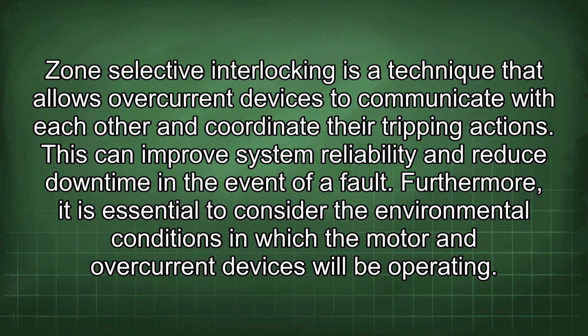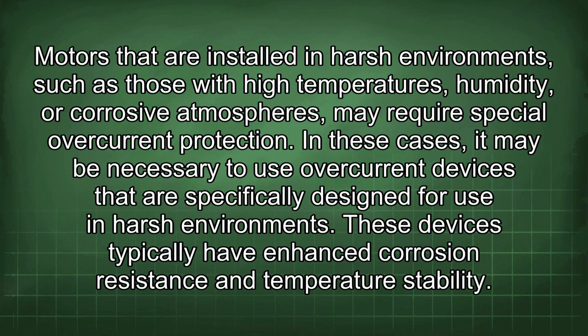Furthermore, it is essential to consider the environmental conditions in which the motor and overcurrent devices will be operating. Motors that are installed in harsh environments, such as those with high temperatures, humidity, or corrosive atmospheres, may require special overcurrent protection. In these cases, it may be necessary to use overcurrent devices that are specifically designed for use in harsh environments. These devices typically have enhanced corrosion resistance and temperature stability.